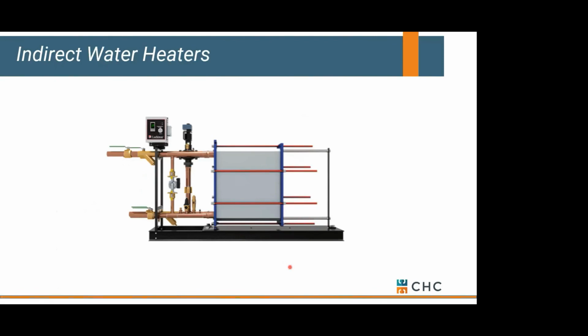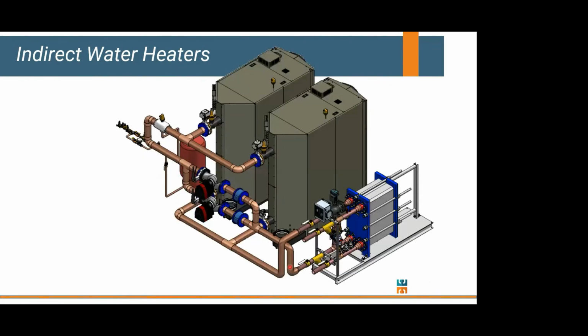Now we've been talking about dedicated water heaters. Let's throw a wrench at that and do something we call indirect. What are we doing with an indirect water heater? What are we talking about? We're talking about using our boilers in this case to indirectly heat domestic water. And how do you do that? Well, you need some type of break, and by break I mean you can't directly take your boiler water and heat domestic. So in this case, our break is a heat exchanger. So we flow hot boiler water through one side of the heat exchanger, and on the other side we circulate it back to a storage tank with our domestic water.